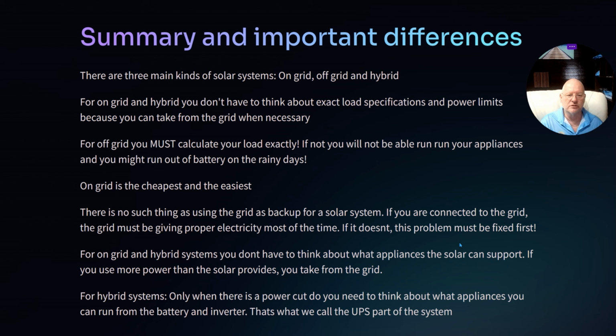Don't think like that, because if you are on the grid, it has to be good. If it's not, it has to be fixed. There are many different ways to fix it, depending on what the problem is, obviously. You can fix it with a voltage regulator, or maybe the transformer is undersized or the cable is too small. But if it's not giving proper electricity, then this must be fixed.